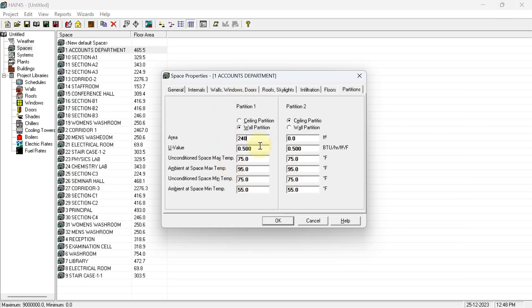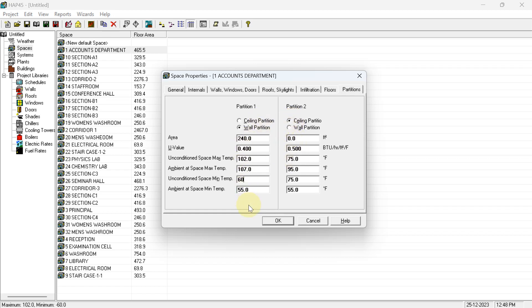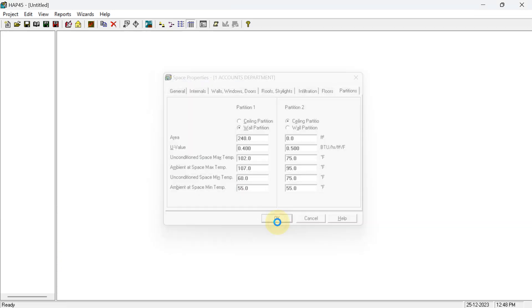Enter the partition wall area as 240 square feet. The U-value for the partition wall from the ASHRAE Handbook is 0.4. Enter the temperatures: summer outside 107°F, unconditioned space 102°F. For winter, the outside temperature is 55°F; inside an unconditioned space the temperature will be slightly higher, about 5 degrees more — so enter 60°F. If there is a ceiling partition between conditioned and unconditioned spaces, enter that detail as well. Hit OK when done.